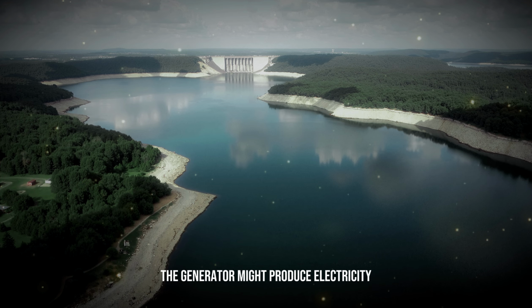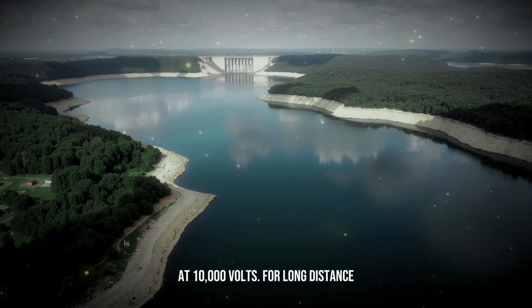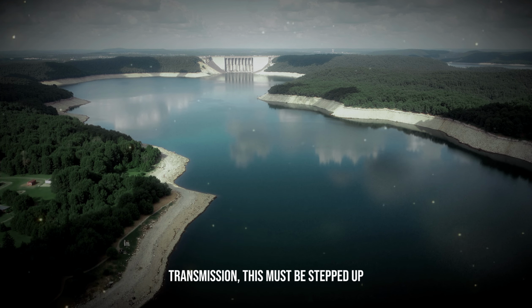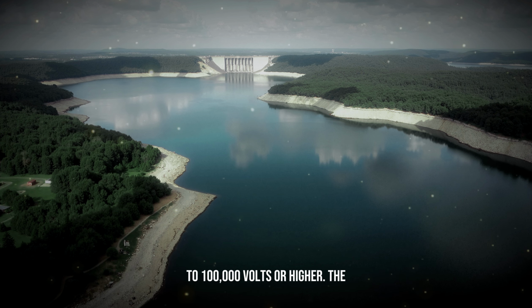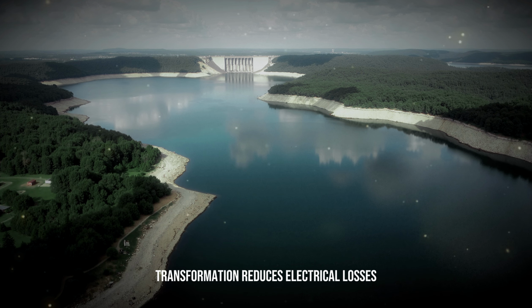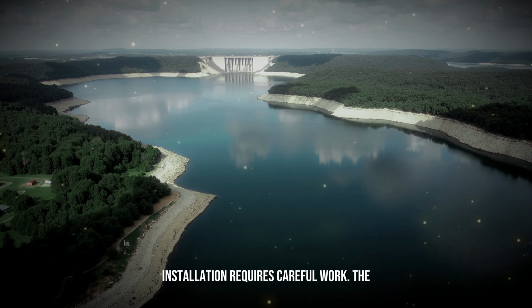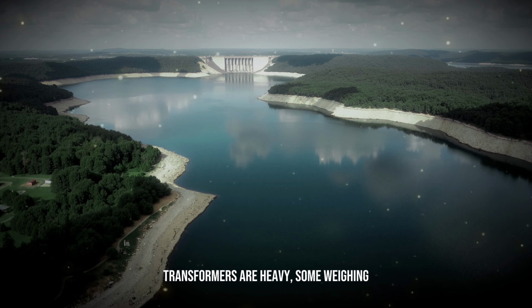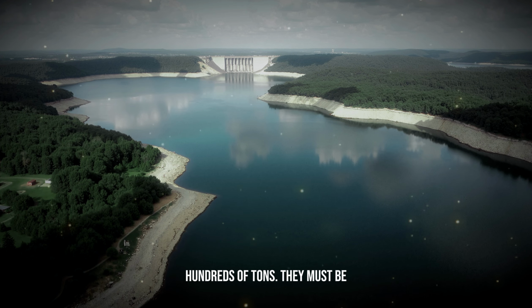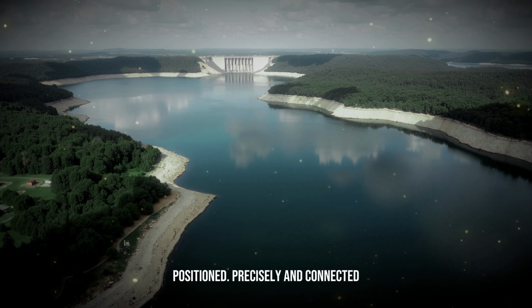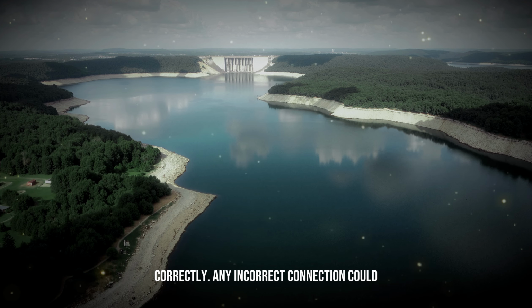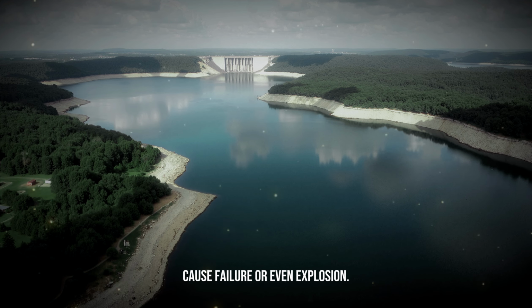A generator might produce electricity at 10,000 volts. For long-distance transmission, this must be stepped up to 100,000 volts or higher. The transformation reduces electrical losses during transmission. Transformer installation requires careful work. The transformers are heavy, some weighing hundreds of tons. They must be positioned precisely and connected correctly. Any incorrect connection could cause failure or even explosion.